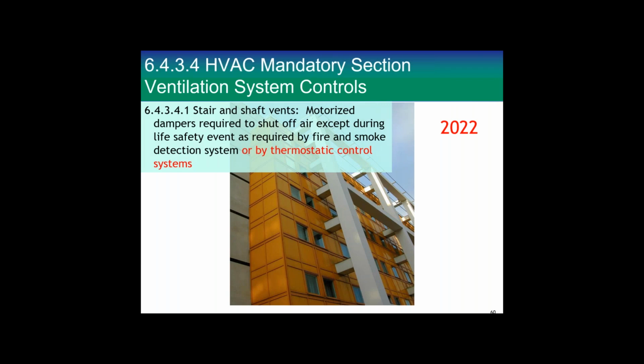Now, in 2022, we've always had trouble with stair and shaft vents. Motorized dampers are required to shut off except during a life safety event or as required by fire and smoke protection systems. Different jurisdictions have different requirements for these kinds of systems. We added thermostatic control systems this time. In the past, it's been a little iffy whether you could use anything like a thermostat to control something for life safety. Now it seems that the way they've rewritten the life safety side of the standard, it is allowable, and we took advantage of that.